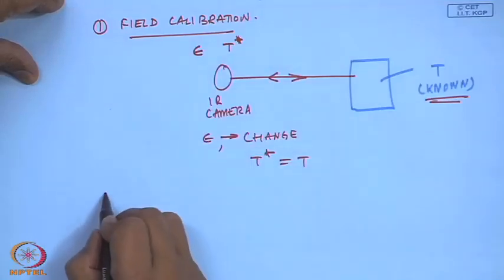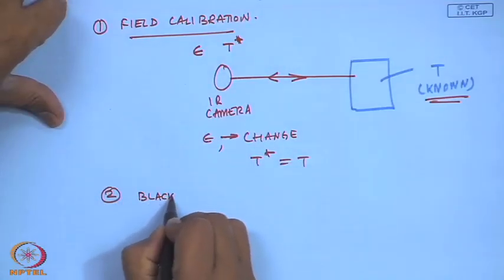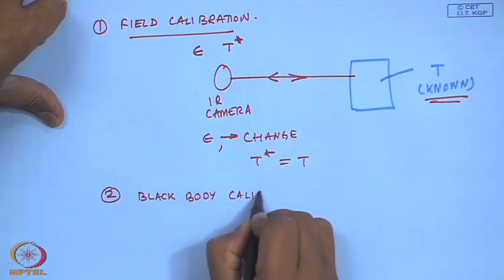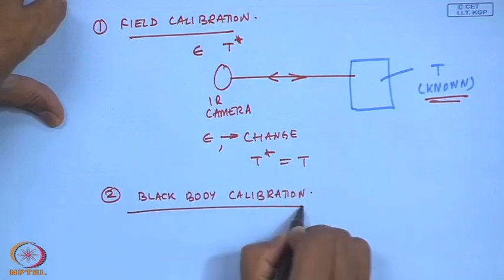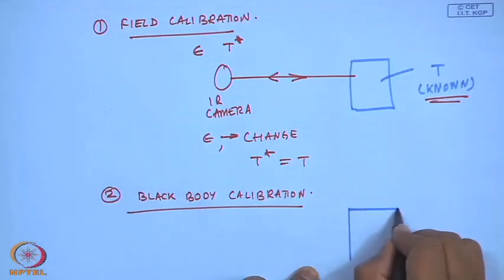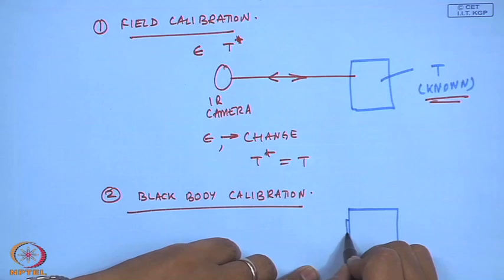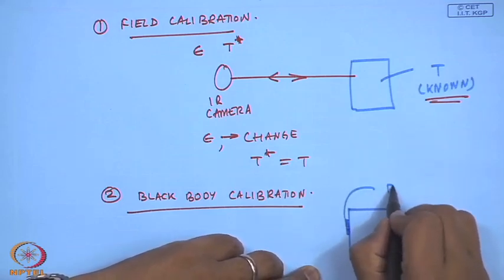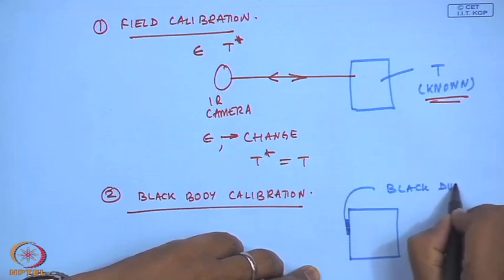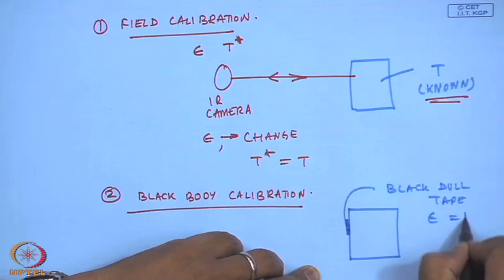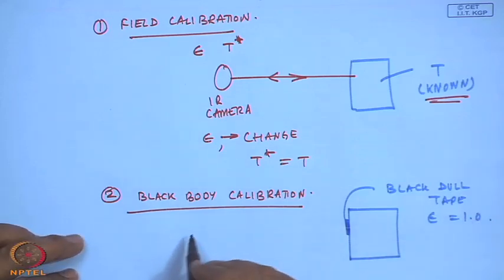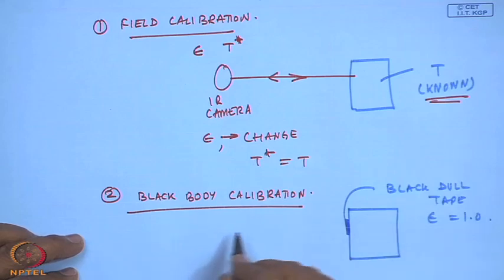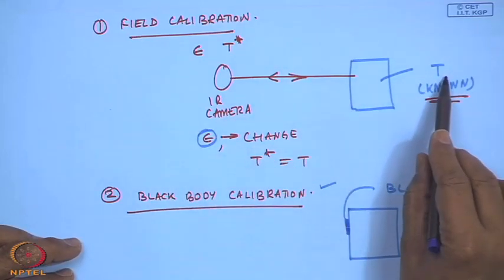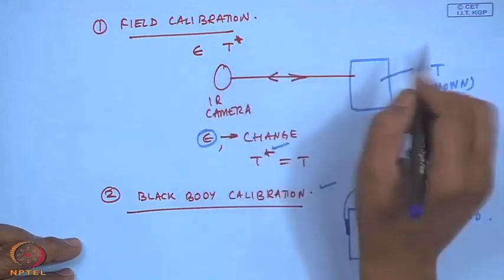That is one method. Next is you can do a black body calibration. In the sense, I will make a body and put some black patch, black tape, dull black tape, so that emissivity becomes 1, and then because the emissivity of this IR camera is set to 1, I will measure the temperature accurately. So that is 1, but in the field it is always good to change emissivity so that your known temperature equals whatever you are measuring by T star in the camera. This is something you have to keep in mind.